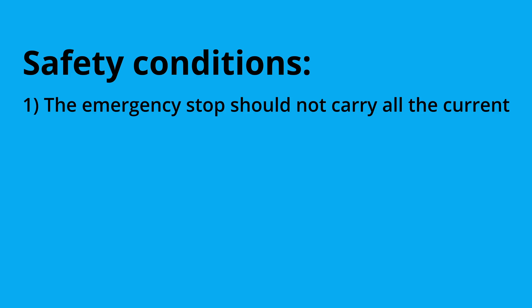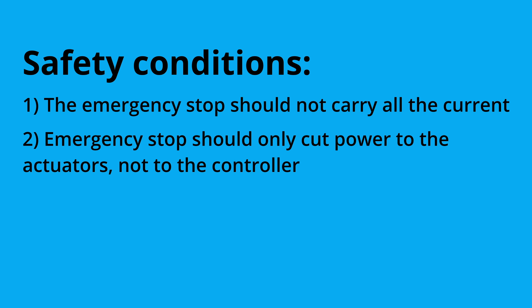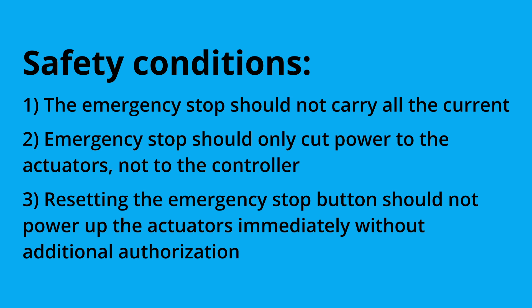When using emergency stop buttons, we want them to meet three safety conditions. Firstly, the emergency stop button should not carry all the current. The emergency stop button should only cut power to the actuators, but not the control system. And resetting the emergency stop button should not power up the actuators immediately without additional authorization.